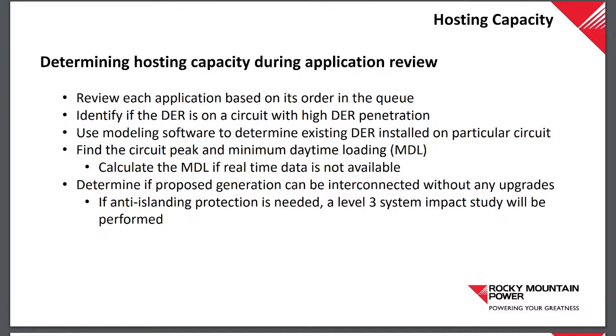So it sounds like it's net minimum daily load for the circuit, because the generation that's already there is offsetting the load, so there wouldn't be an import or anything coming down the circuit, right? Yeah, there's two ways to look at it. We can either use that actual minimum load, or we can use that load and add in a percentage of the existing generation, because not all the generation is at 100% when it's at that load. There are some websites where you can check that on a given day and time, in a given region, the solar output was at 72%.